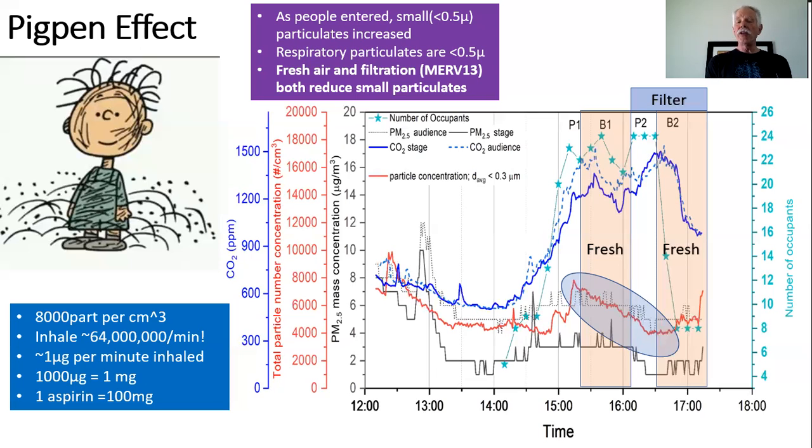And you can see that there's a continuing decrease of the particulates, but once the fresh air fan was turned off, the recirculating air fan did nothing to remove CO2. The CO2 started to increase again, but the particulates started to drop.